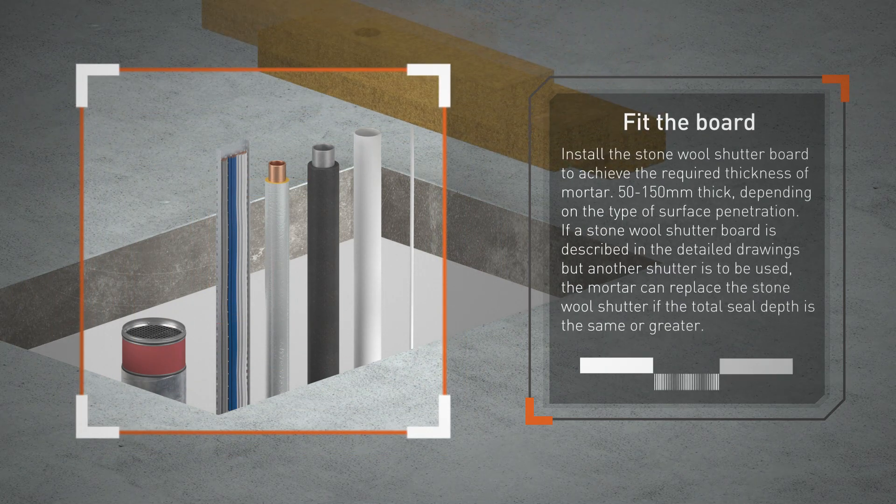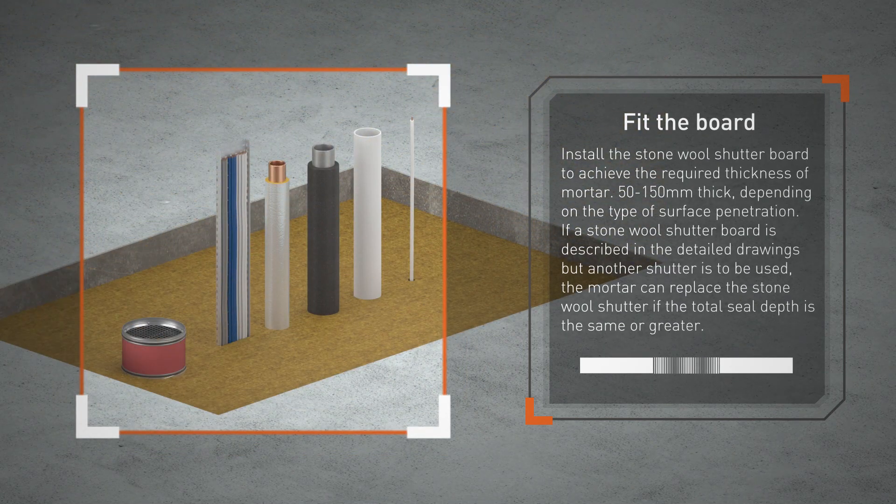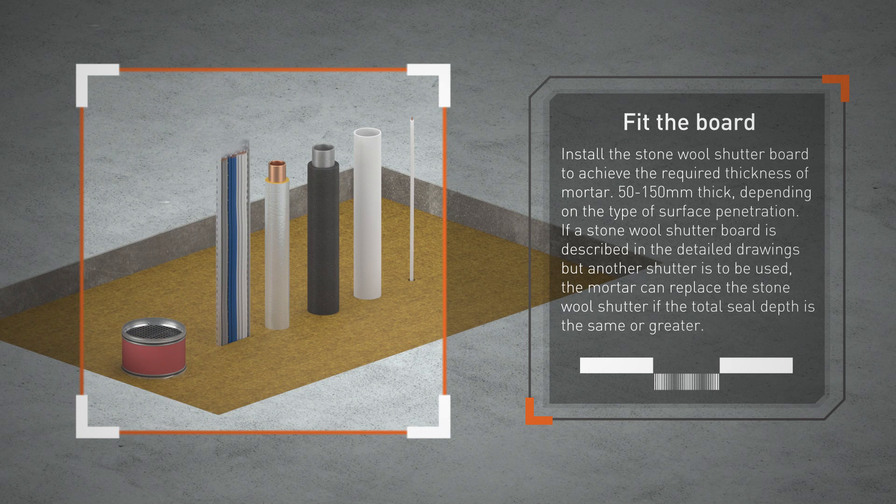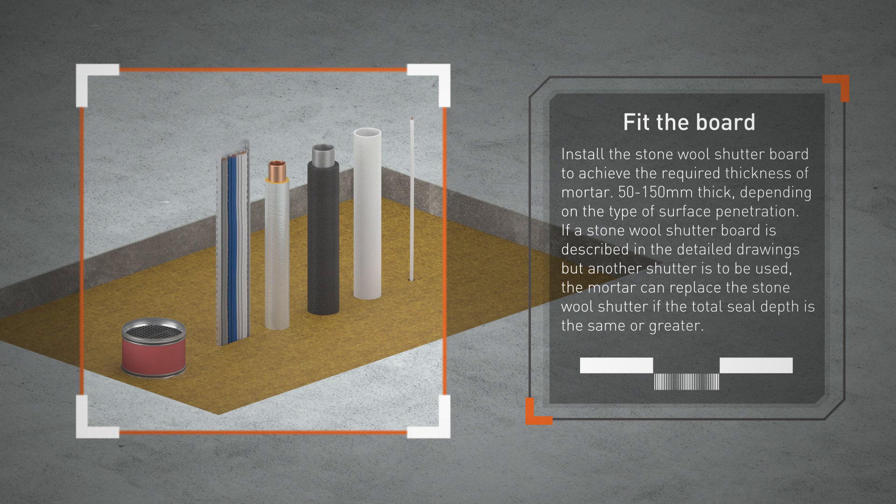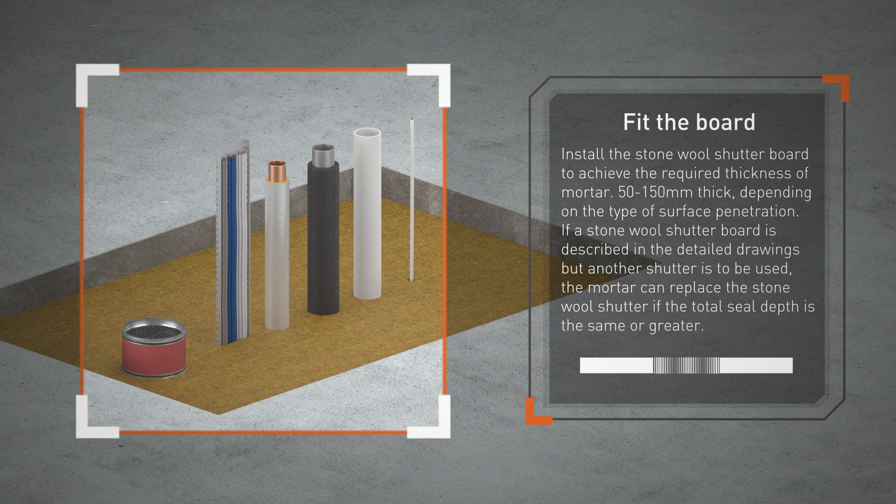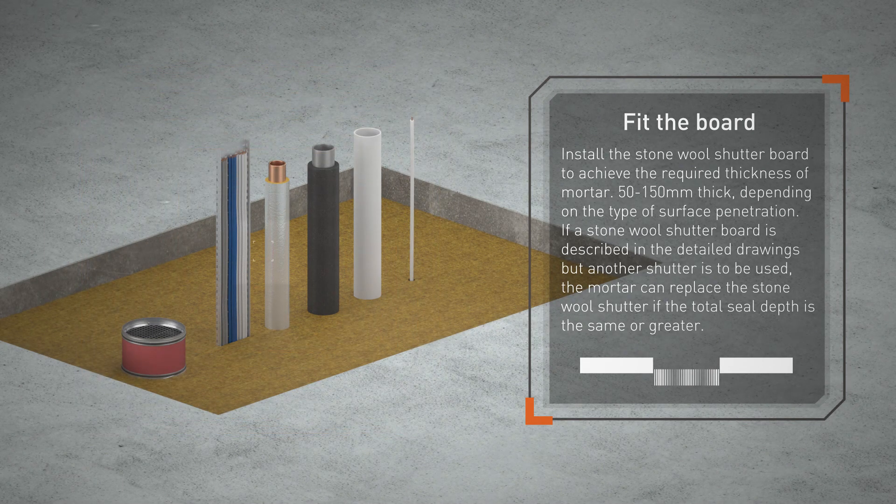Install the stone wool shutter board to achieve the required thickness of mortar 50-150 mm thick, depending on the type of surface penetration. If a stone wool shutter board is described in the detailed drawings but another shutter is to be used, the mortar can replace the stone wool shutter if the total seal depth is the same or greater.